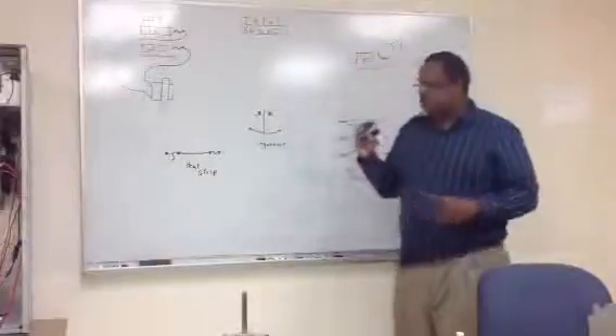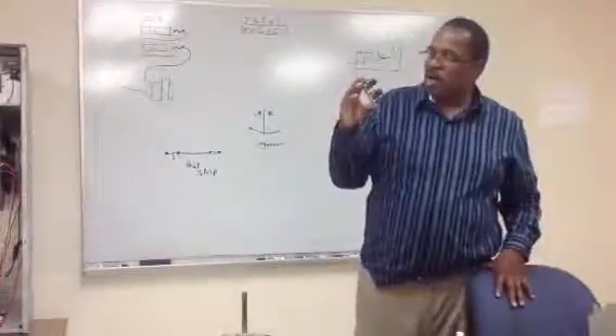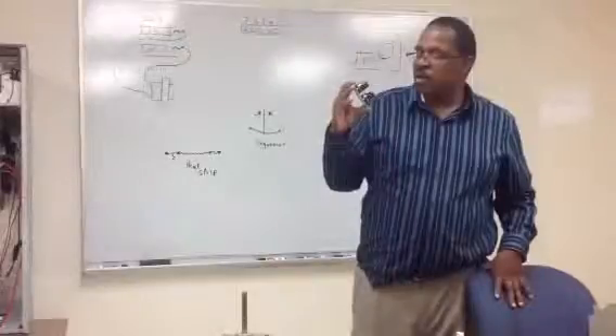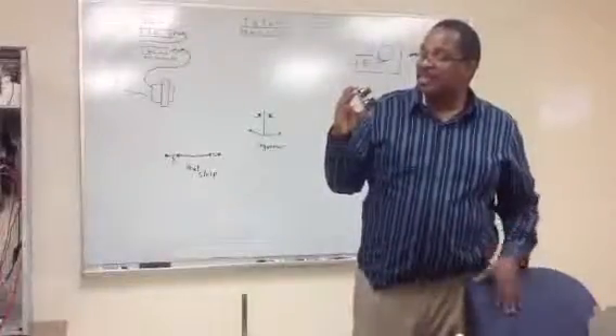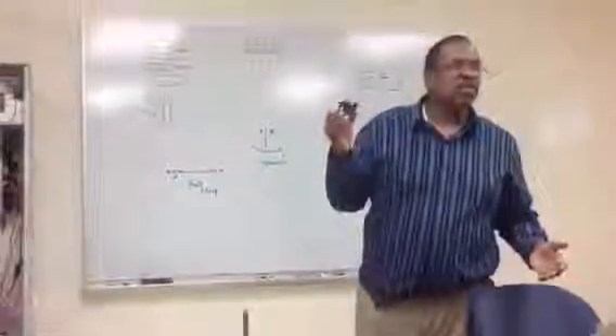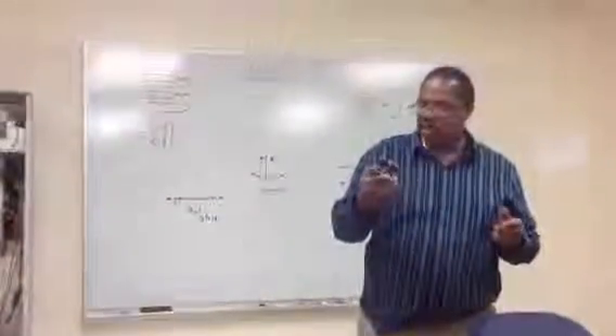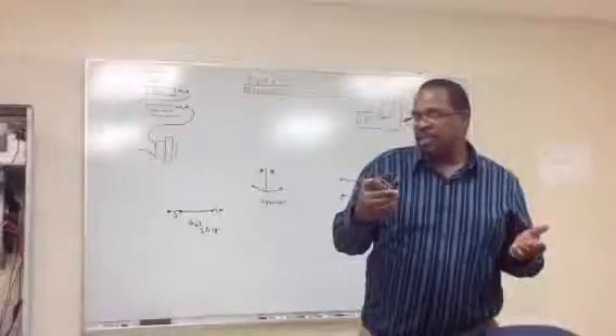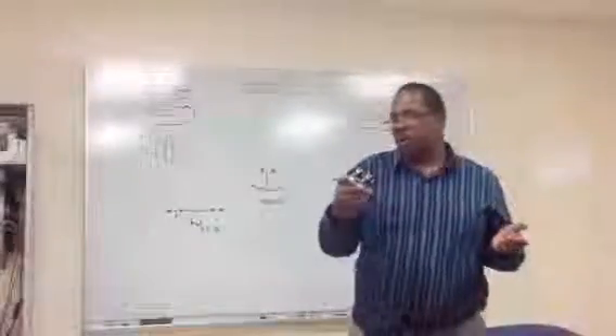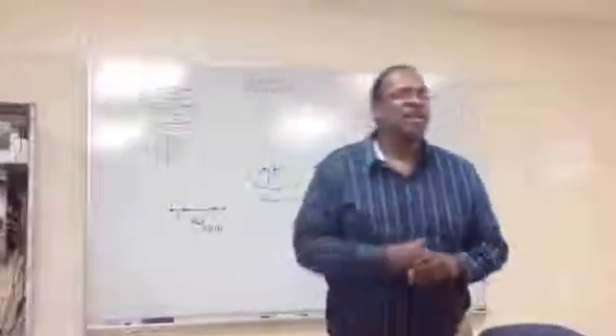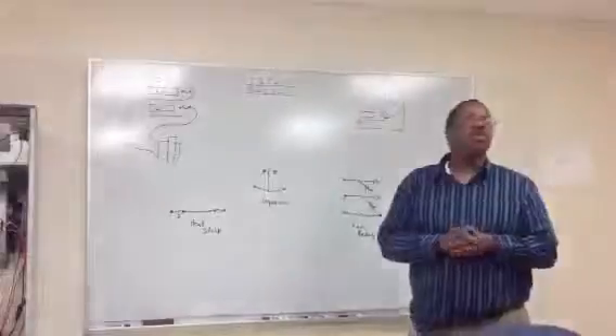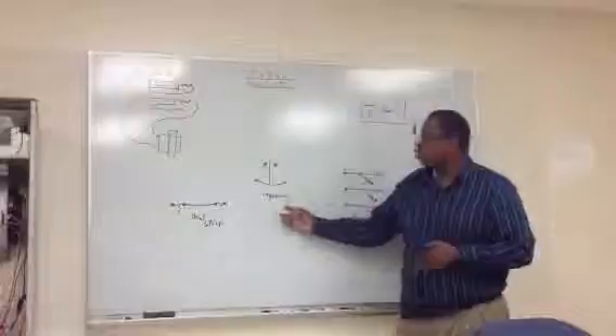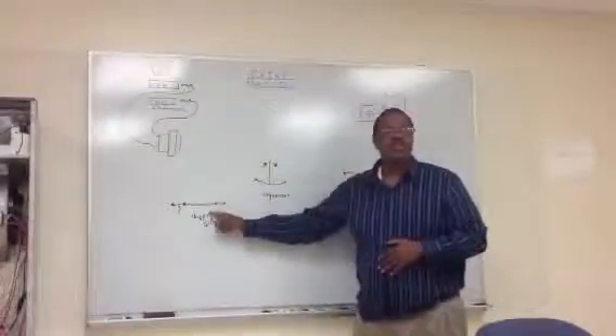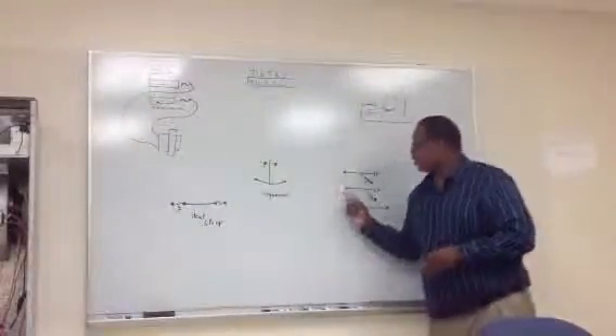Now, there are ways of reading the sequencer that let you know how much time it will take for it to close and how many seconds it will take for it to open. It depends on that particular sequencer. They usually have a C for closing, and it'll let you know, and an H will let you know how long it takes to open or close. So just keep that in mind. But that's not really super important as long as it works. Most of them will do what they're supposed to do. So the sequencer is going to control our what? Heat strip. Our fan relay is going to control what?